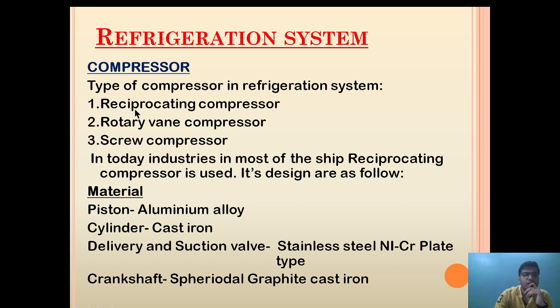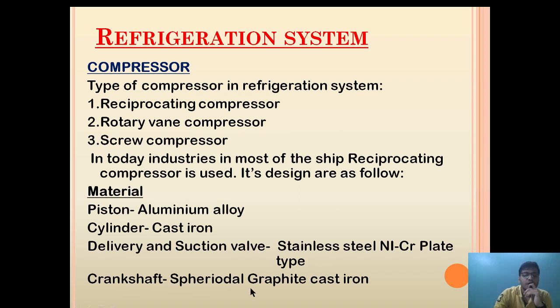The types of compressors used in a refrigeration system are: first, a reciprocating type compressor; second, a rotary vane compressor; and third, a screw type compressor. In most of today's industry, the reciprocating type compressor is used. The materials used are: pistons made of aluminium alloy, cylinder is of cast iron, and the delivery and suction valves are made of stainless steel nickel-chromium plate — to give roughness and toughness, and to allow quick and large volume operation. The crankshaft is made of spheroidal graphite cast iron to withstand high fatigue stress.